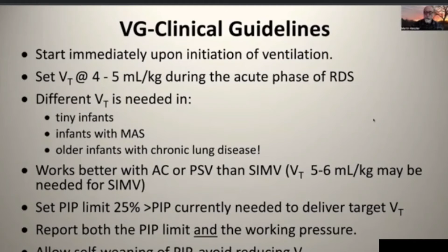You want to keep your inflation pressure limit relatively tight to the actual tidal volume that's needed. And you need to, of course, keep track of not just what the pressure limit is, up to which the adjustment can occur, but also what is actually being used. And of course, we want this to take advantage of the self-weaning ability of volume-targeted ventilation. One of the advantages of volume-targeted ventilation is you need fewer blood gases, and weaning occurs in real time. The machine doesn't wait for morning rounds. It doesn't wait for the next blood gas, it weans you in real time, which is why more rapid weaning occurs.